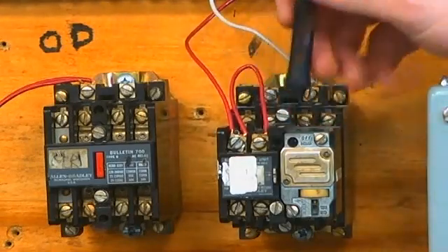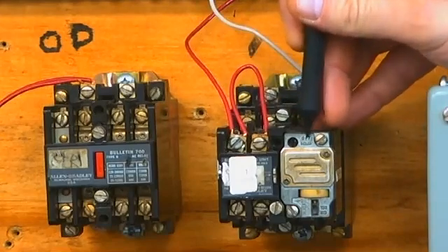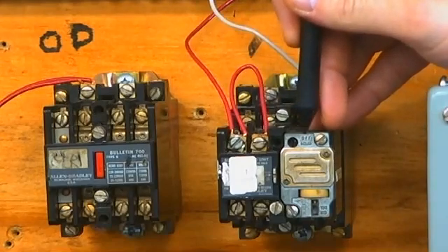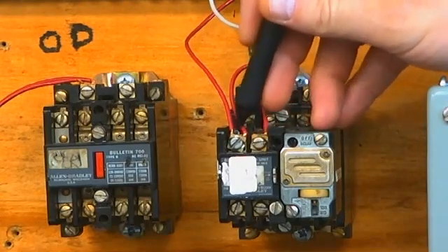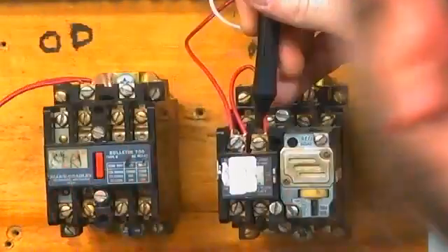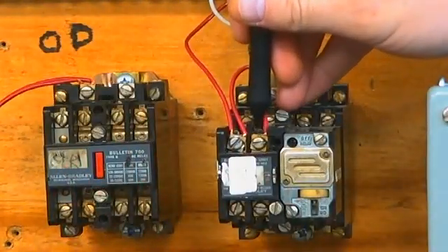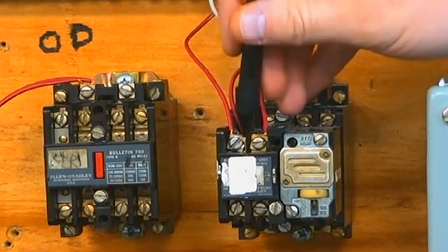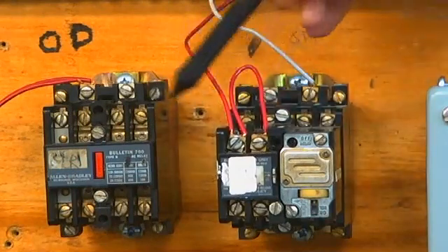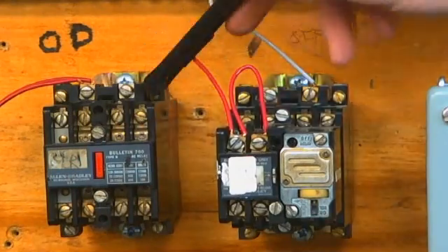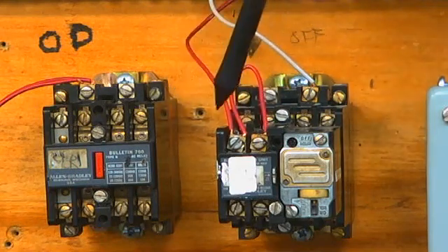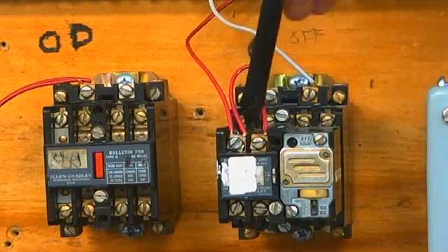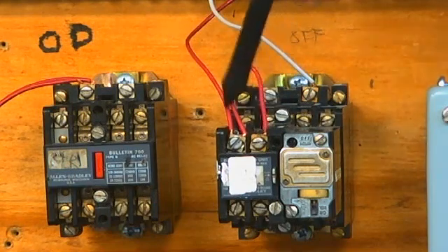This one, I don't know if you can read it, but it says off delay right now. We'll get into that more in a second, but there's two sets of contacts on the timer. One on the left is normally open, the one on the right is normally closed. All right, so same thing with the back part, the relay. If you wanted to change those to normally open or normally closed, if you wanted to make them both normally closed, you can do that by taking this thing apart. That's the beauty of NEMA.